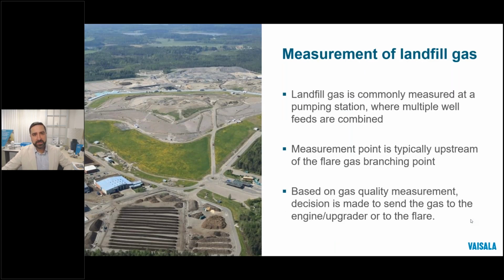And landfill gas is another staple source of methane for CHP and RNG production, but the composition of that gas presents its own unique challenges. Varying qualities and impurities often require more complex treatment options that need to be consistently monitored to reduce risk and maintain throughput. We commonly see initial measurement at the point where multiple well feeds are combined, which is due to the expensive nature of monitoring. Individual wells are often only checked manually with portable devices rather than with fixed instruments. We'd like to see more incoming measurements to divert certain streams to different uses, but of course my opinion is a little bit biased towards selling more instruments.